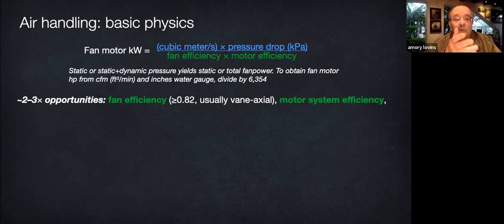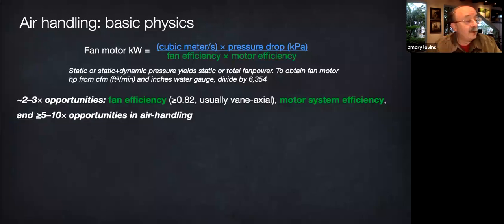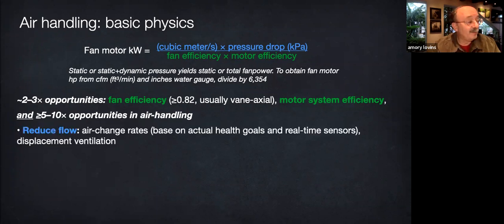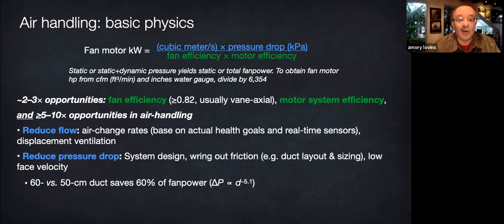Sometimes more, but of course you should do those things, but reducing flow and pressure drop often offer much larger opportunities, worth at least 5 to 10-fold. And you should do all of the above. Which comes first? Reduce the flow first, then reduce the pressure drop, because both of those will make the fan and the drive system smaller, therefore cheaper, helping to pay any extra costs of making it super efficient as well.